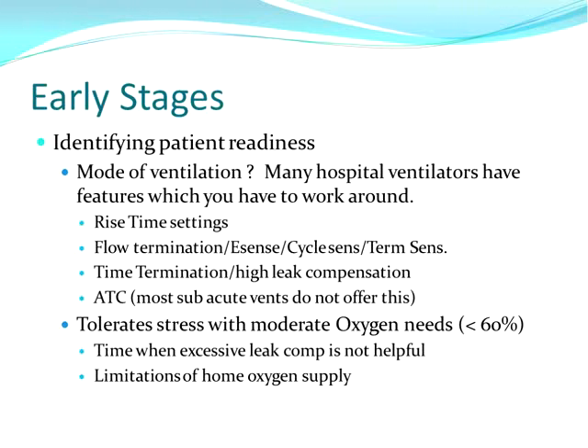Most subacute and home care ventilators don't offer ATC, or automatic tube compensation. So recognizing this when you're making your transition is very important. I know I find this a lot when I go into a critical care setting and I'm helping to make a transition onto a subacute care vent, that many times the physicians will say, oh, but we had to go up on the settings, the patient isn't doing as well on the subacute ventilator. And so for those of us who've been in respiratory therapy for over 20 years, we recognize there was a long time of doing critical care ventilation before automatic tube compensation was even available on ventilators.